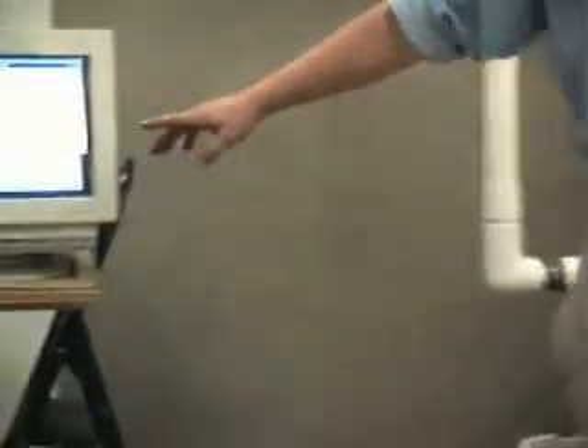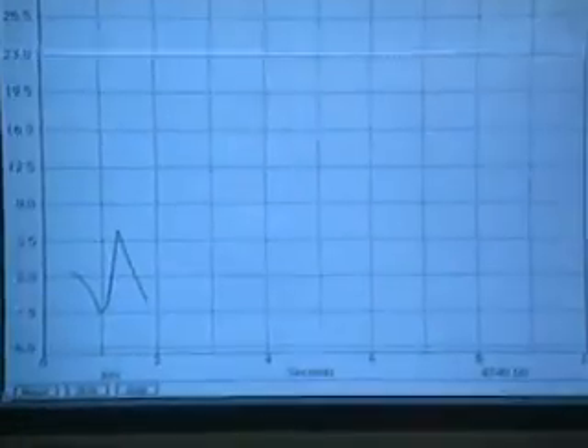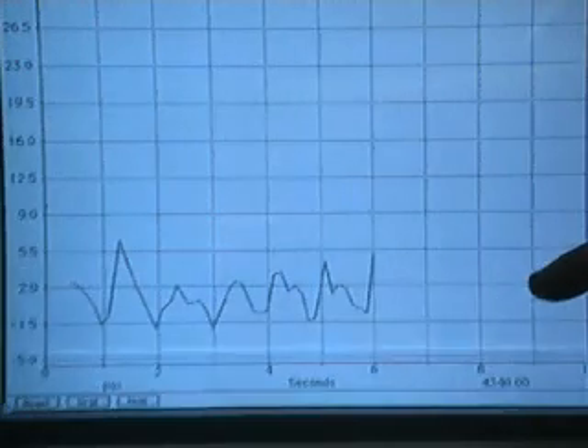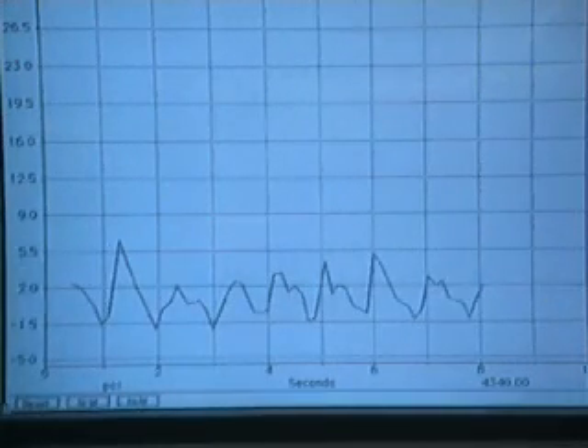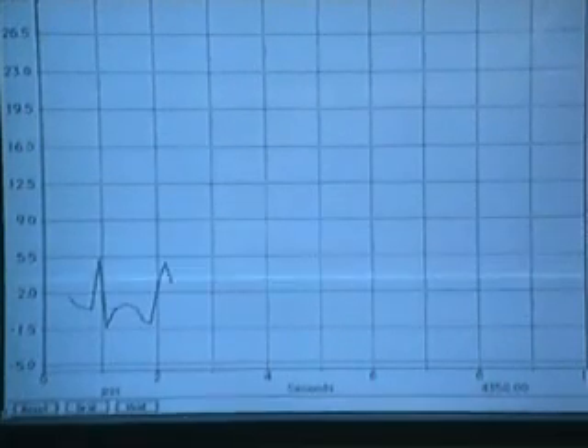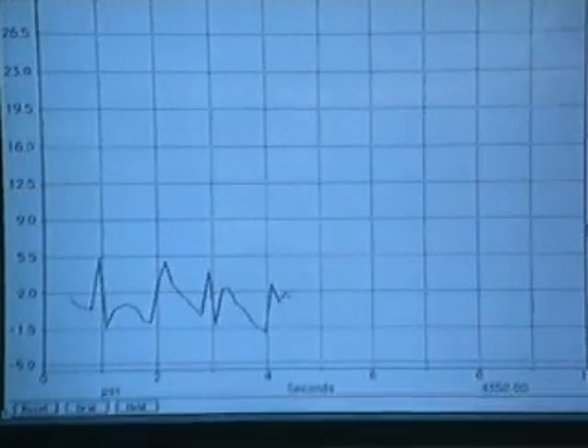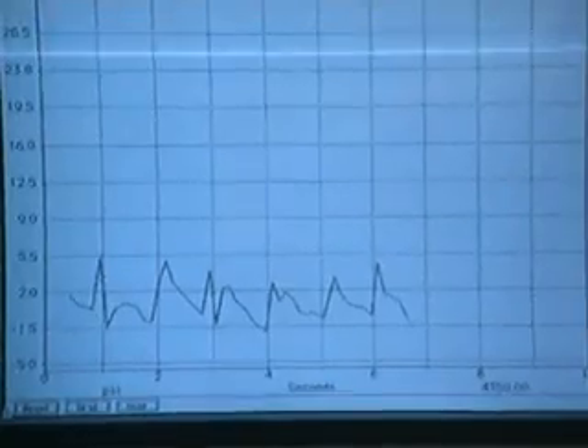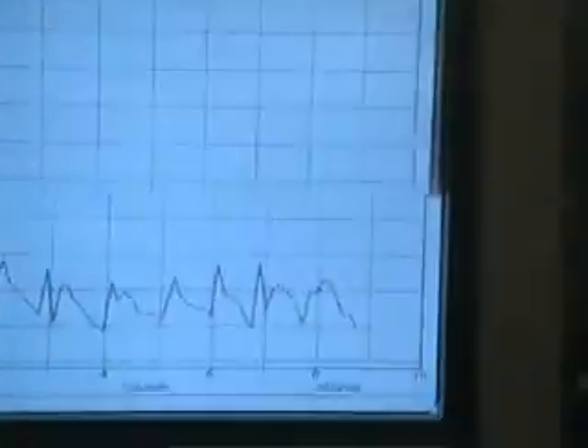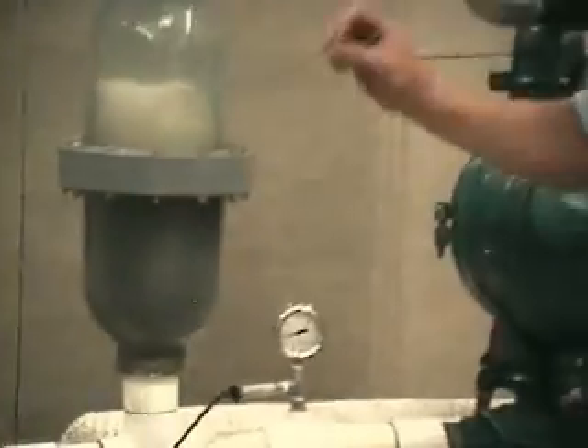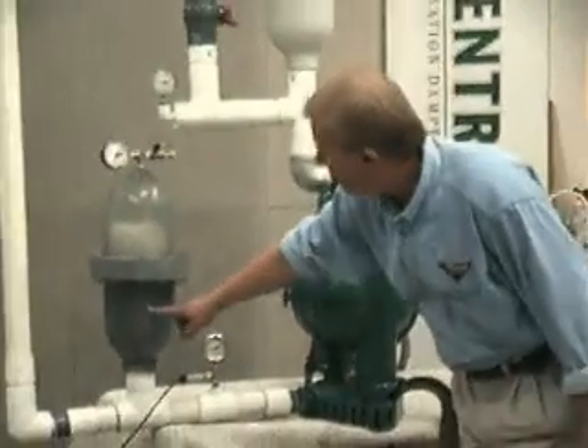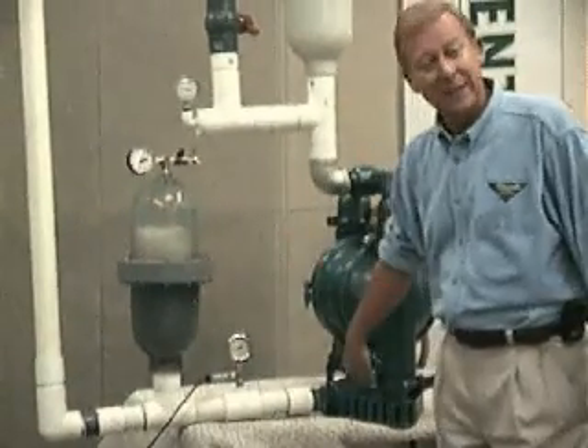Now, if you notice, on the transducer, the pressure spike has been absorbed by the inlet stabilizer and is now averaging around 2 psi. That amount of pressure spike is well within the limit of the air diaphragm pump, and no damage will occur to its diaphragms. The valve balls will seat more positively. There's less chance of cavitation because we're accumulating liquid right at the inlet.